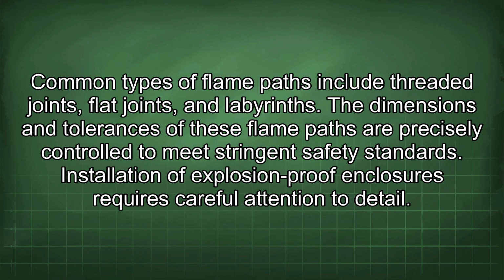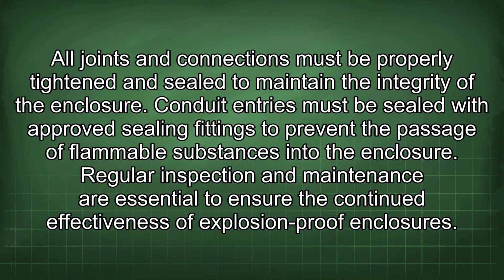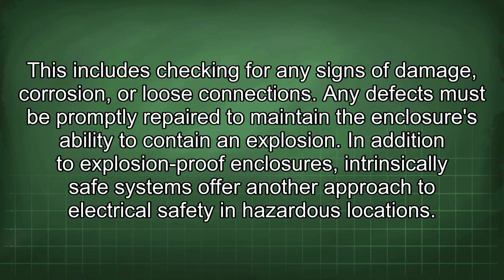Installation of explosion-proof enclosures requires careful attention to detail. All joints and connections must be properly tightened and sealed to maintain the integrity of the enclosure. Conduit entries must be sealed with approved sealing fittings to prevent the passage of flammable substances into the enclosure. Regular inspection and maintenance are essential to ensure the continued effectiveness of explosion-proof enclosures. This includes checking for any signs of damage, corrosion, or loose connections. Any defects must be promptly repaired to maintain the enclosure's ability to contain an explosion.